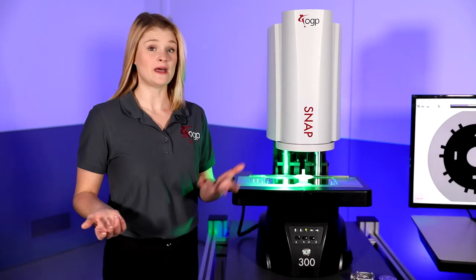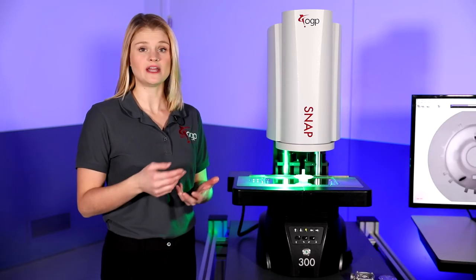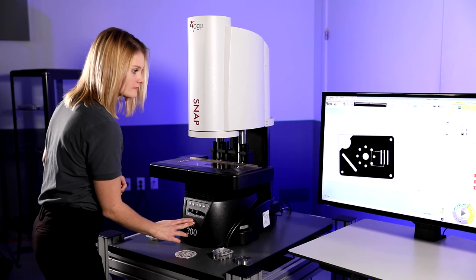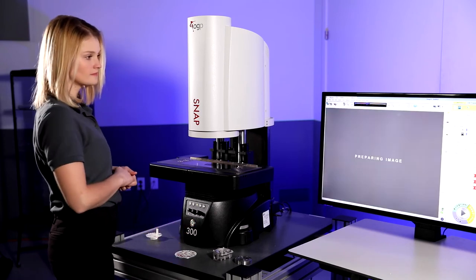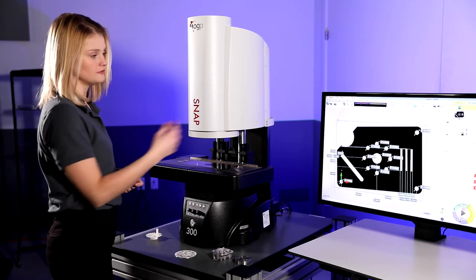For those that have already been registered, AutoID automatically opens the measurement routine and measures the part regardless of its orientation, eliminating the need for complex fixturing.